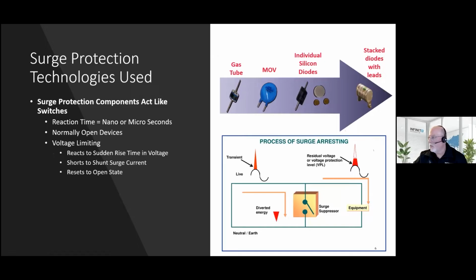Okay, so kind of simply, these surge components that we just looked at are usually in parallel between, let's say, the line and the neutral, or it could be a data plus and data minus, or a DC plus and DC minus. And it's a switch. It's basically what it is. So it's normally open until it reacts to the sudden rise time of voltage. Then the switch closes, shunts the surge to ground, and then opens again. So the lightning event is a microsecond duration, and power spikes from the utility company, well, they should be that, but that's quite different from what's called sustained overvoltage. That's another whole issue, and surge protectors are not designed to mitigate that. They'll die. They don't like that.